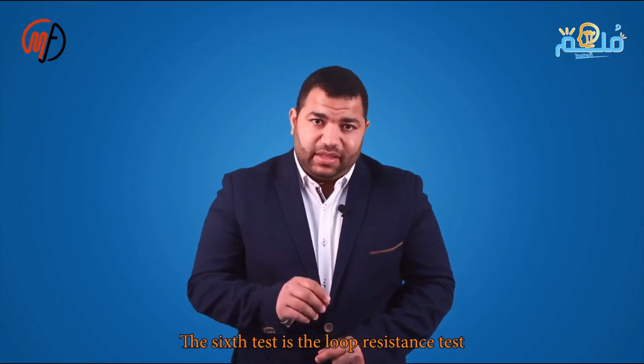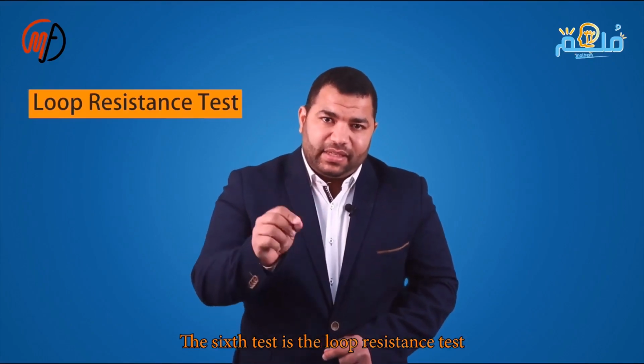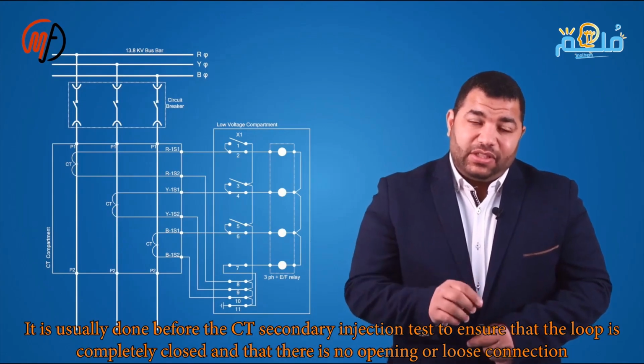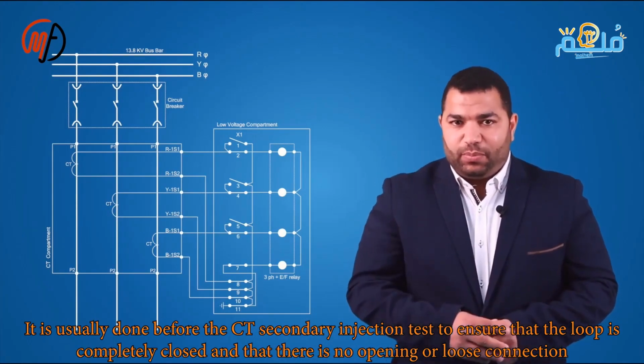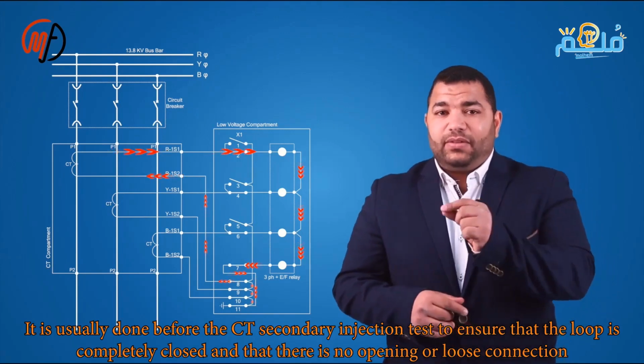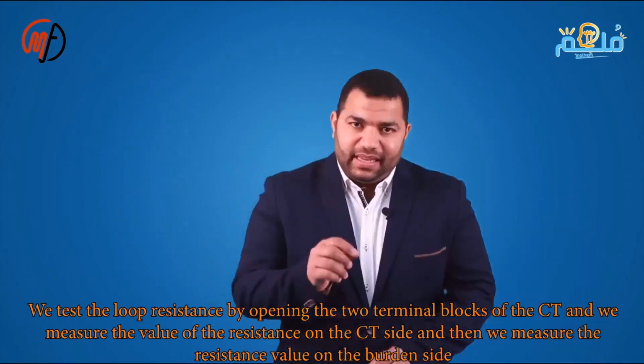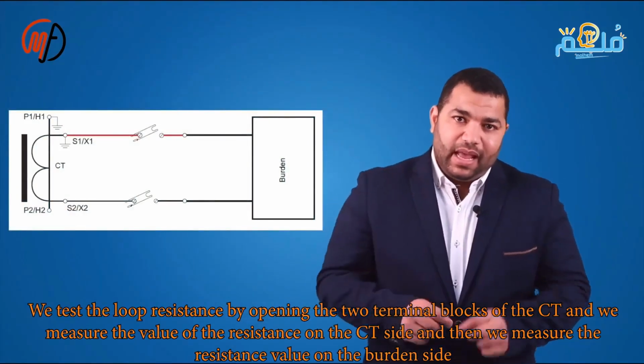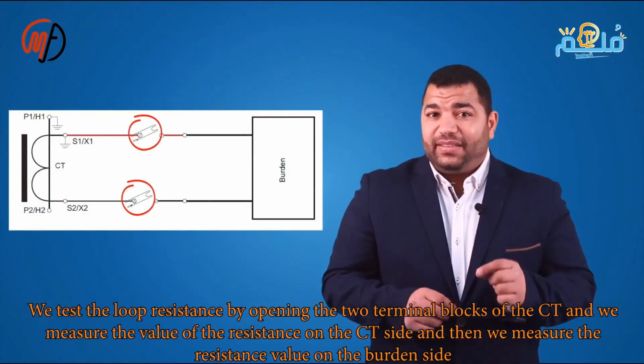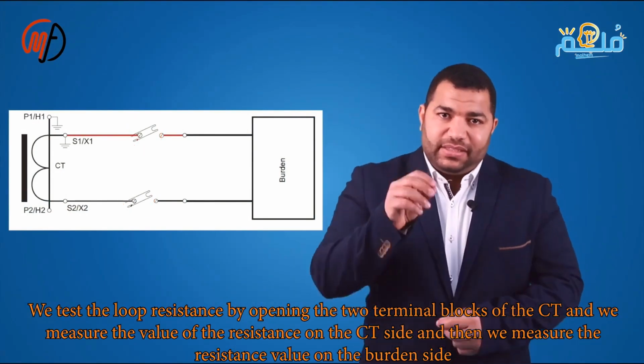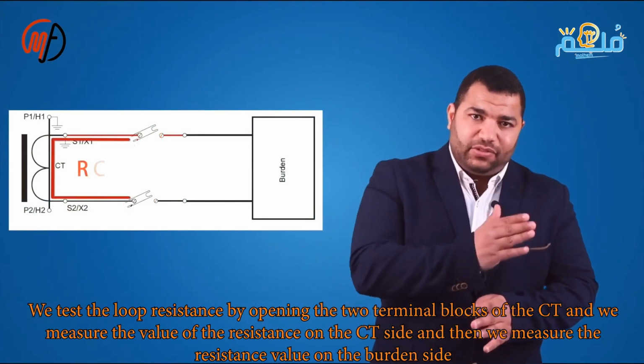The sixth test is the loop resistance test, and this test is conducted before the CT secondary injection test to ensure that the entire loop is correct and there are no open circuits. We perform the loop resistance test by opening the 2 terminal blocks at both ends of the secondary side of the CT. We measure the resistance from the CT side and then measure the resistance from the burden side.